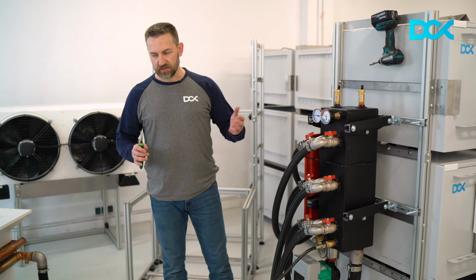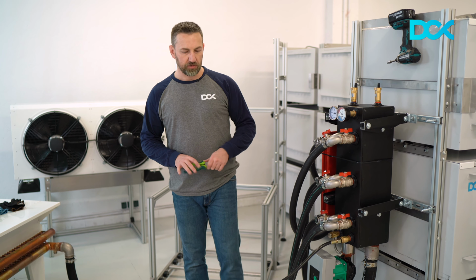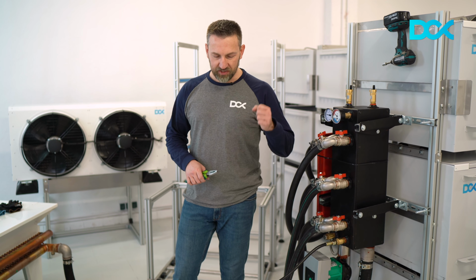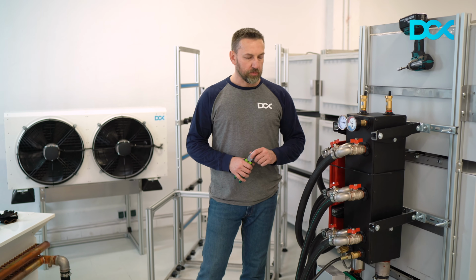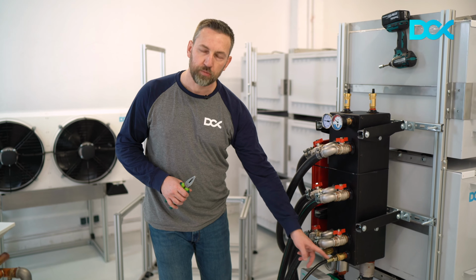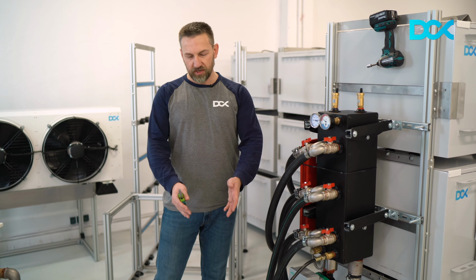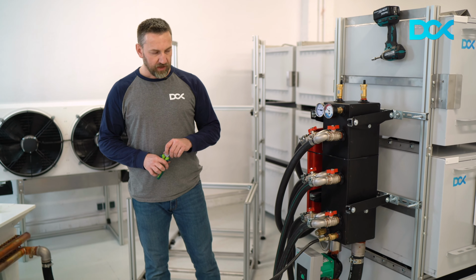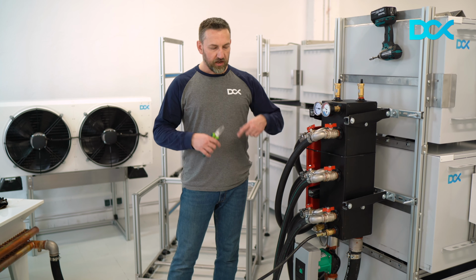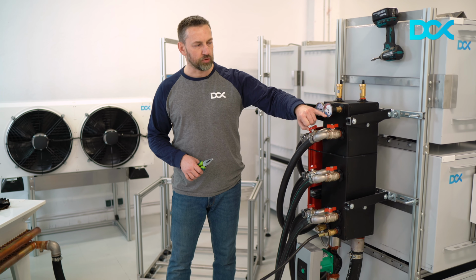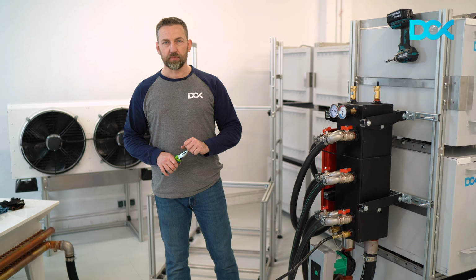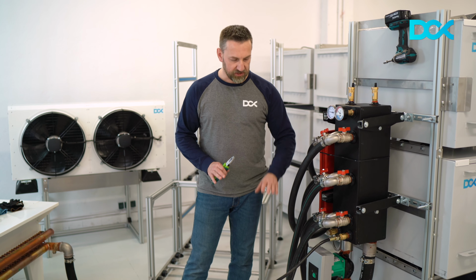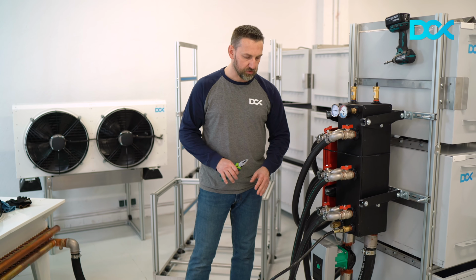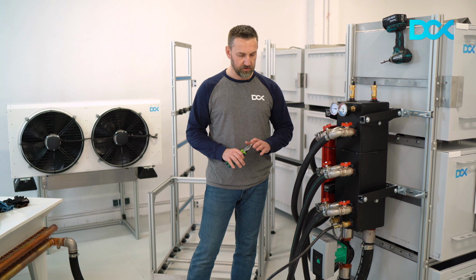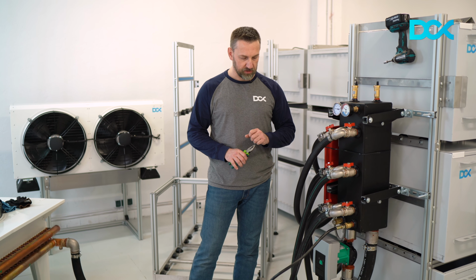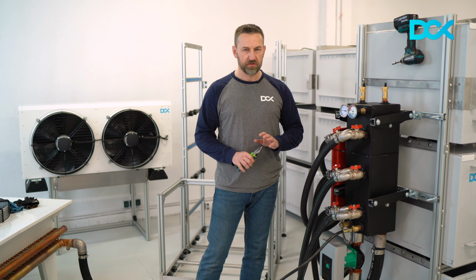We just filled that system. It took us maybe, I don't know, 20 minutes or so to do that, and most of that time was just wiggling with that handle here on that pressure pump. You must know that you may also connect any circulation pump to pre-fill the system. So now we're first connecting a pressure pump, so less hassle with that manual one, and then you are able to pre-fill the unit. After that, just pressurize the system up to 2 bars maximum with that manual pump. So after you filled the system, you start the pump. This is what we did. We didn't start the pump too early. Only after the installation was pre-filled. And now we must observe what will happen.